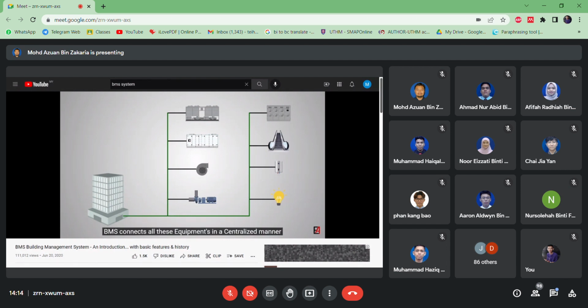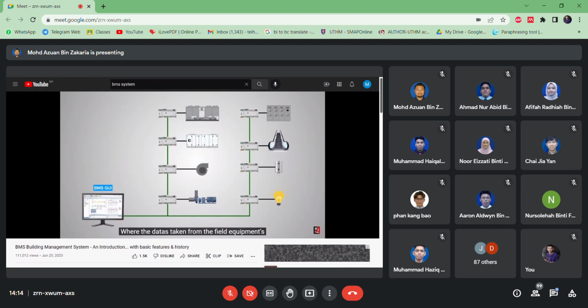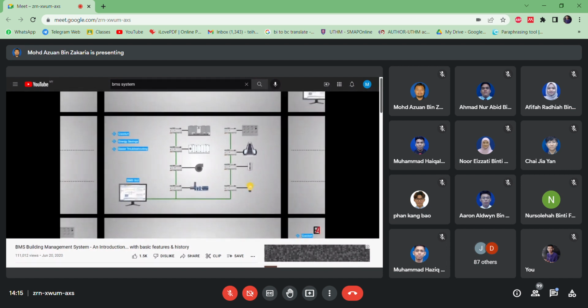BMS connects all these equipments in a centralized manner. BMS controls, monitors, and optimizes the equipments using hardware and software components. It is a package of intelligent microprocessor-based controllers which connect directly to these equipments at field level. The controller sends data to a management system where the data taken from the field equipment is translated into a graphical user interface format. BMS provides comfort to building occupants, energy savings to the client, and easier troubleshooting opportunities to the building operator. The BMS system comprises three main levels.